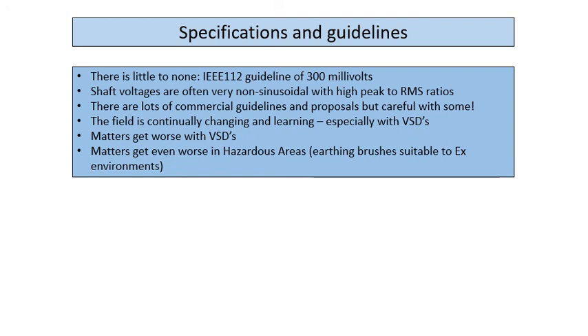They're also often very non-sinusoidal with high peak to RMS ratios. So you've got to be careful the way you measure it. You can have a shaft voltage that's got a sinusoidal component of 100 millivolts, and it has peaks of much more, like that one I showed earlier, the one with both brushes open. There's lots of commercial guidelines and proposals, but be careful with some. I think that you're going to get the commercial interests taking precedence. So look at things sensibly.